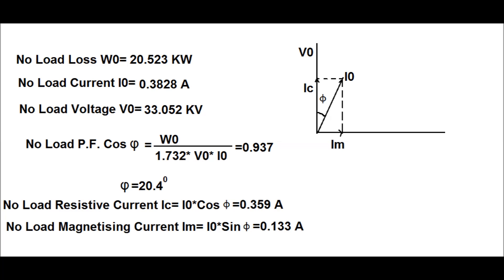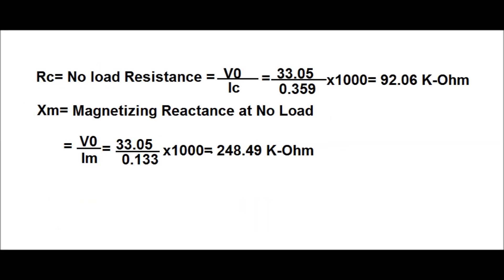The no-load resistive current is Ic = I₀ cos φ = 0.359 A, and the no-load magnetizing current is Im = I₀ sin φ = 0.133 A. From these, the no-load resistance is Rc = V₀ / Ic = 33.05 kV / 0.359 = 92.06 kΩ, and the magnetizing reactance is Xm = V₀ / Im = 33.05 kV / 0.133 = 248.49 kΩ.